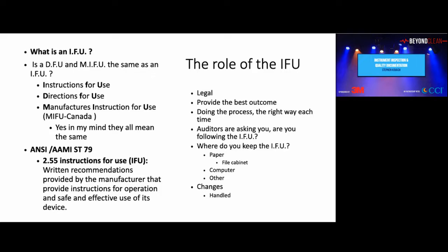And I'm just going to take it from ANSI AAMI ST79. Written recommendations provided by the manufacturer that provide instructions for operation and safe and effective use of its device. And why is that important? Legally. This is what you should do each and every time. If you decide to do something else and there is an issue or fault, your facility takes on that legal responsibility if you haven't done your due diligence to show your way is better, or it didn't go through some committee or risk management. And there are enough lawsuits out there that show when people have not followed the IFU that they are sued and there are settlements made. And unfortunately, a lot of the times patients are injured.